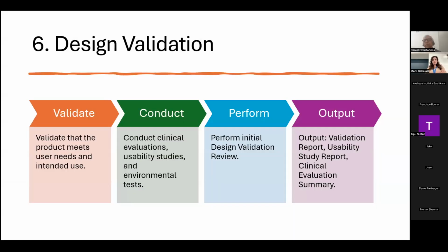And the next is the design validation. We talked about the difference between design verification and validation. Here you are validating that the product meets the user need and the intended use. You're conducting your clinical evaluation, your usability studies, and the environmental tests. Then you're performing the design review, design validation review, and again, your final summary report. So these are all what we call certain stages in the development: at your design verification, your summary report, design validation, summary report. And usually the design engineers and the manufacturing engineers will be involved with this, and will get them vetted by the quality engineers, because you really need some checks and balances. We know we do our job very well, but it's always good to have an external party, a party who's not involved in your process, verify those. So the checks and balances will be there to be sure everything is taken care of, so that nothing has slipped between the cracks.